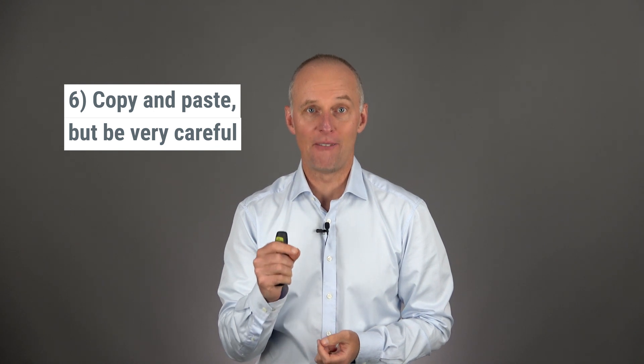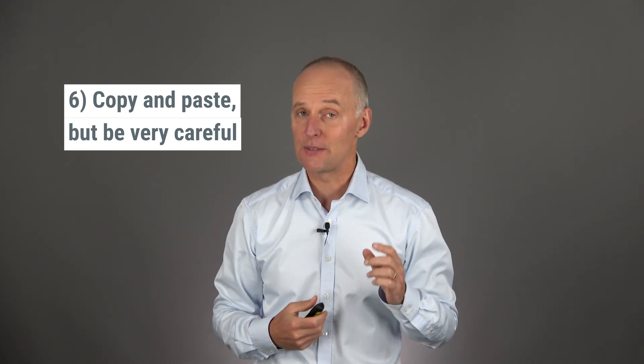Number six: if you're creating a brand new product, you won't have any background risk management work to start from, so everything is done from scratch. If there is a similar pre-existing product, you can consider yourself lucky — feel free to copy text from a previous hazard traceability matrix from the predecessor product. But here is a big fat warning: the devil is in the details. If you do copy text from a previous risk management file, be very careful when reviewing what you've copied and pasted so that you don't forget any risks or miss that the risk is different for the new version of the product. It's very easy to make this kind of mistake.